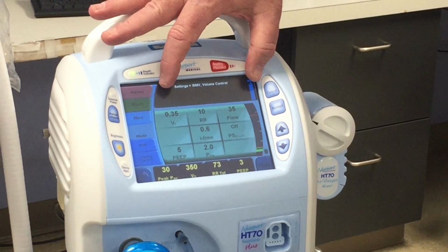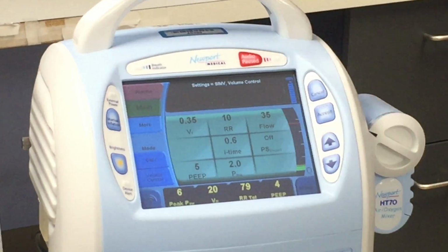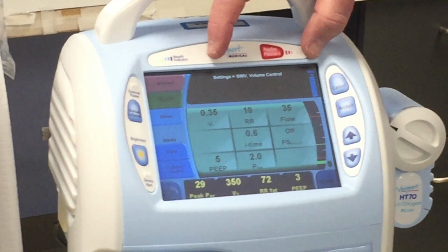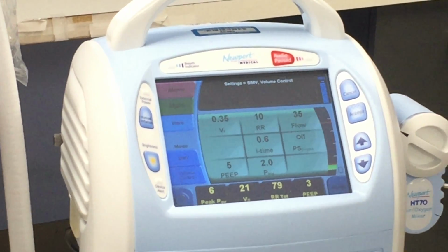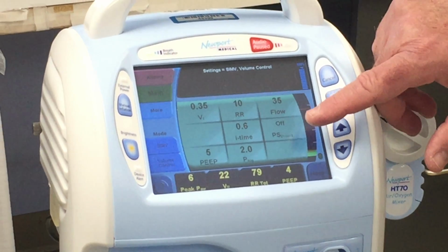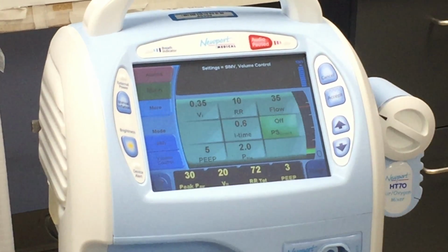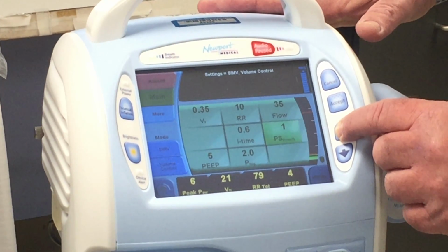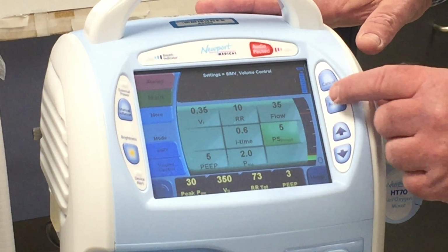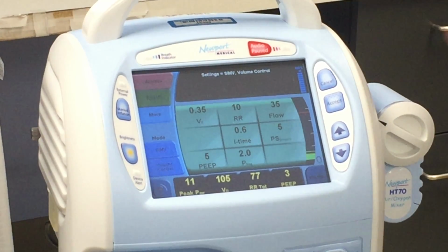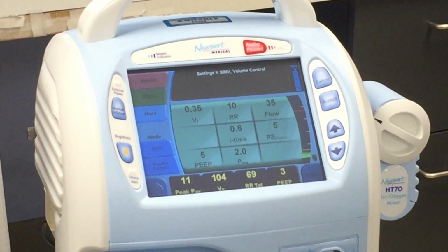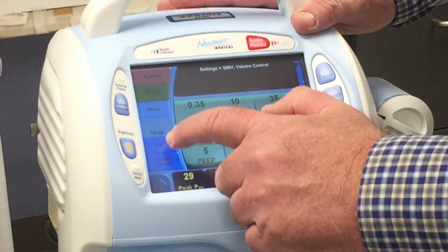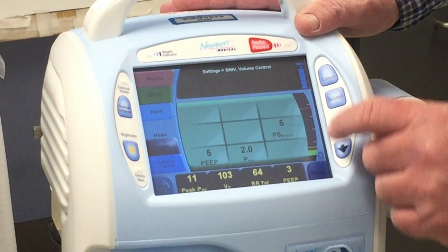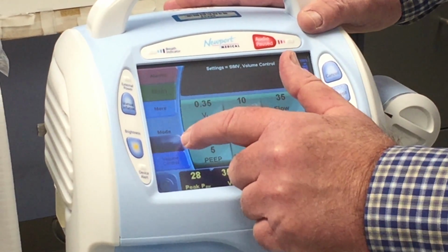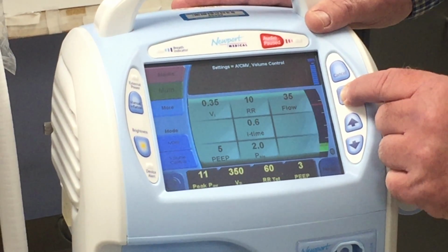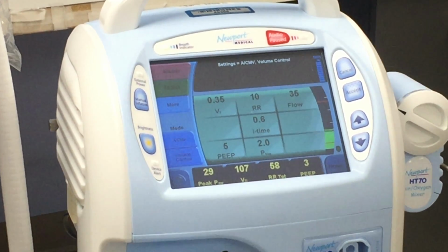Okay. Up here you can see this is our message screen. It lets us know where settings are: SIMV, volume control. Right now our pressure support is off. If we wanted to add pressure support as well, we want to add 5. Now we're in SIMV plus pressure support. Okay. We want to change it to assist control. We hit our mode, assist control, accept. Okay.